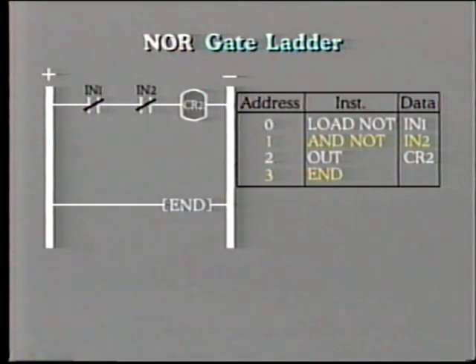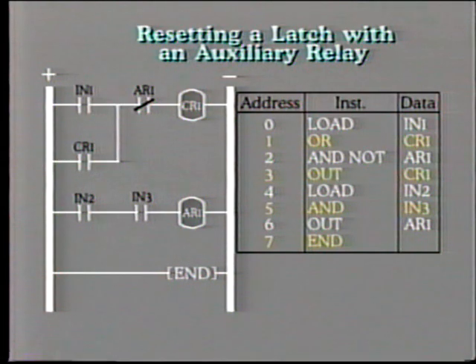The NOR gate logic is similar, except that the two input contacts are in series. In this case, if either input 1 or 2 receives an input signal, its contacts will open and consequently de-energize the output relay. This logic circuit shows the arrangement for latching and unlatching, that is, resetting. In this arrangement, the IN1 contact is closed temporarily by holding a push button. This, in turn, energizes the control relay CR1, which closes the seal-in contact. When the push button is released, IN1 contact opens, but the circuit remains latched in. In order to reset, that is, unlatch the circuit, input contacts IN2 and IN3 must both be closed to energize auxiliary relay AR1. This, in turn, opens the auxiliary relay contacts and unlatches the primary circuit.